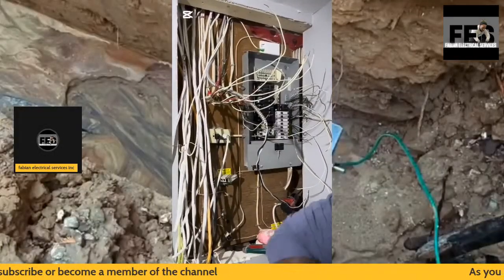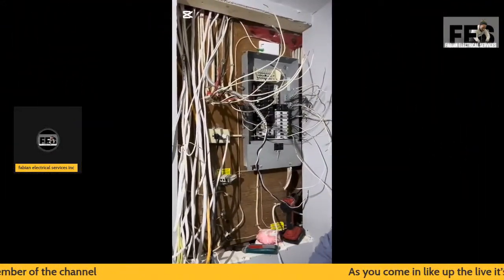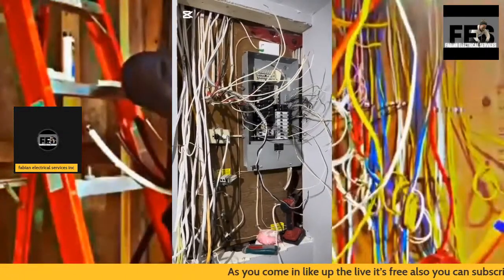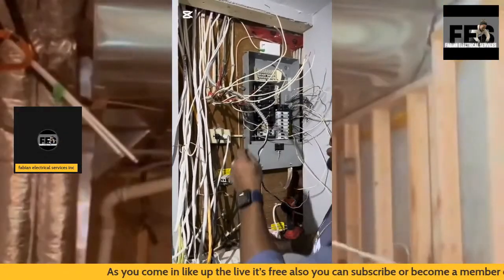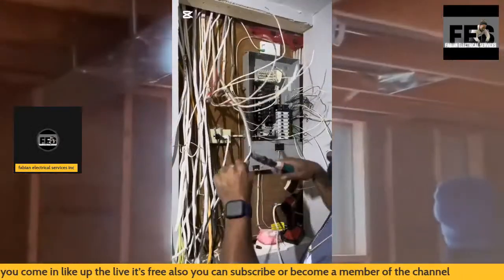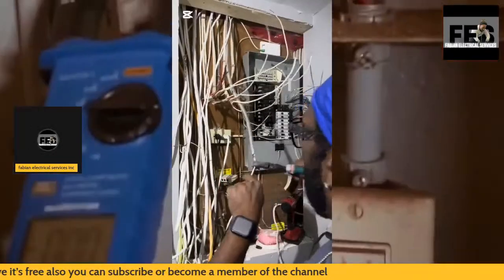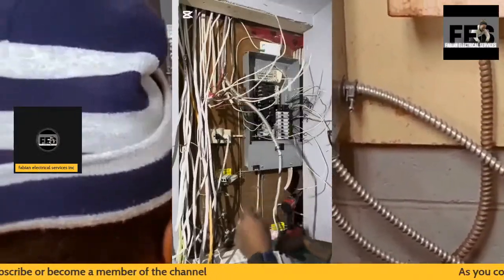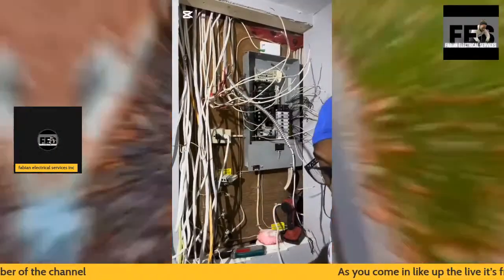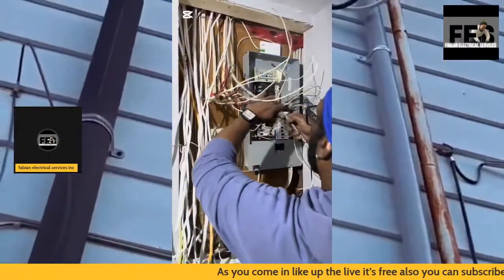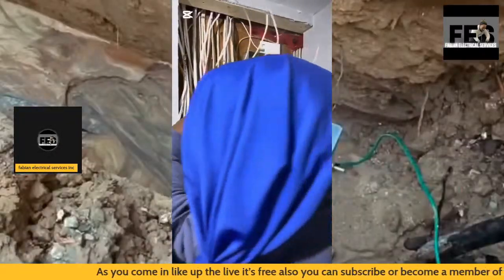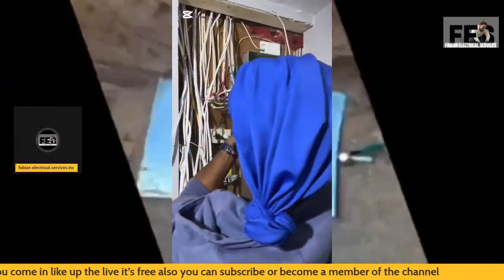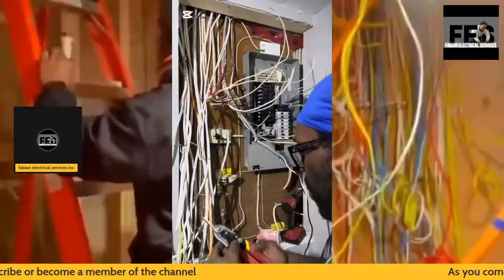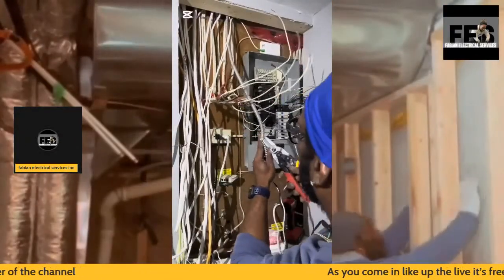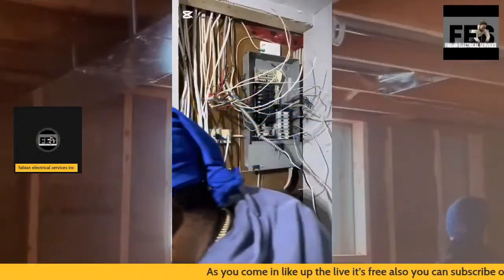So the panel had to be swapped out to an Eaton 100 amp panel, which has the proper breakers I can install. When it comes to panel or service installation, I like to remove my wires from the panel and label them before putting them back in. It helps with the troubleshooting process. You might be asking why.